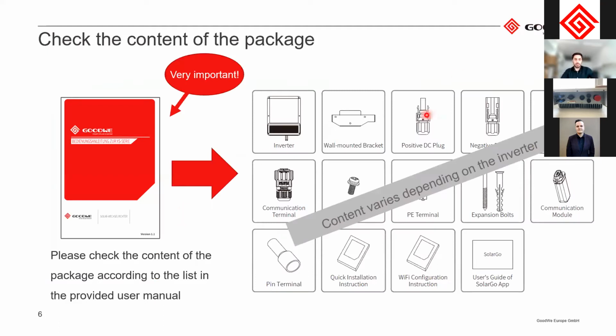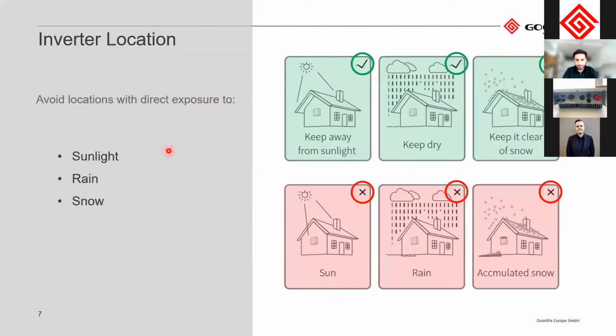Before you start installing it, please check the content of the package. It differs depending on which inverter you have, so check the manual and make sure the package corresponds to what's included in the manual. There are different locations where you can install it. Our inverters have IP65 ratings, so they can be installed outside. However, we recommend keeping them away from direct sunlight, otherwise they will heat up quite quickly, and also keep them dry and clear of snow.